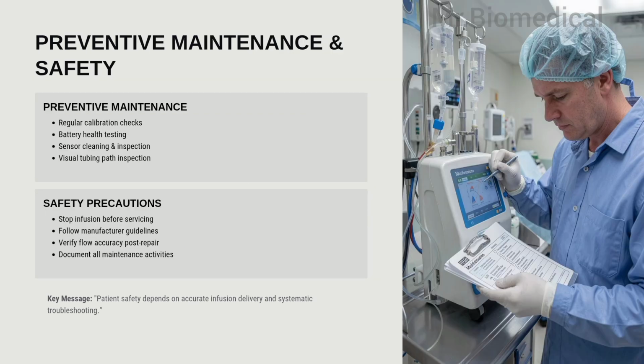Preventive maintenance is the best way to reduce failures and improve reliability. The important maintenance activities include regular calibration checks, battery health testing, sensor cleaning and inspection, and visual inspection of tubing, parts and connectors. While servicing the device, always follow safety precautions. Stop the infusion before maintenance, follow manufacturer guidelines, verify flow accuracy after repair, and maintain proper service documentation.